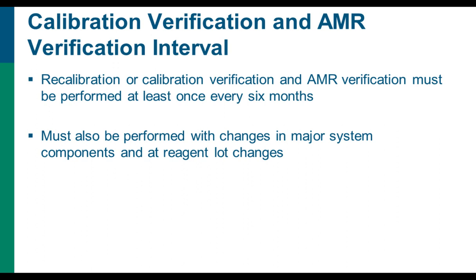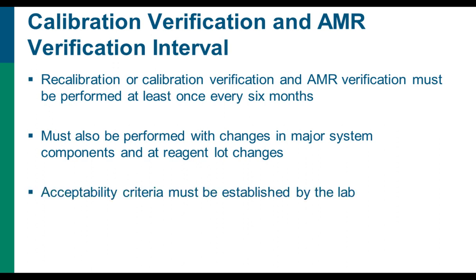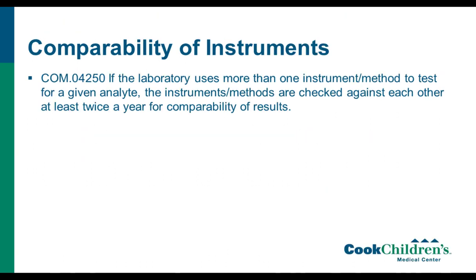So what we try to do is order enough reagents to get us to 6 months. If you order your reagents more frequently, every month or so, you're going to have to do calibration verification as often as the reagents show up. So we try and order about 6 months of reagents at a time so that we're only doing calibration verification around the 6-month requirement. And again, the acceptability criteria must be established by the lab.